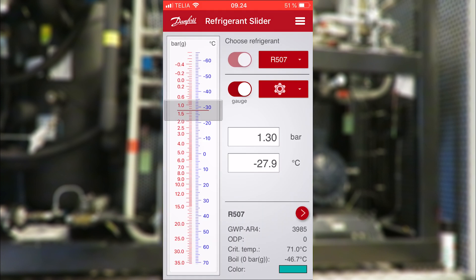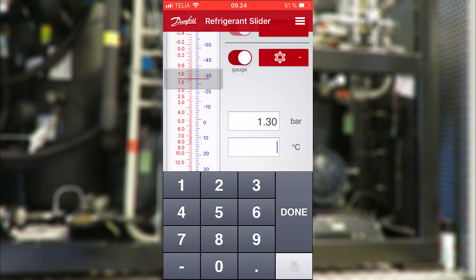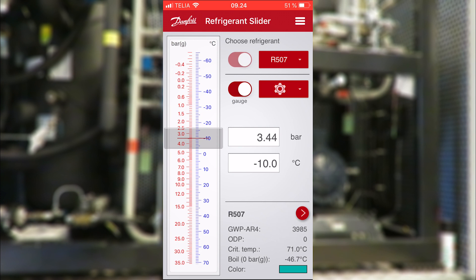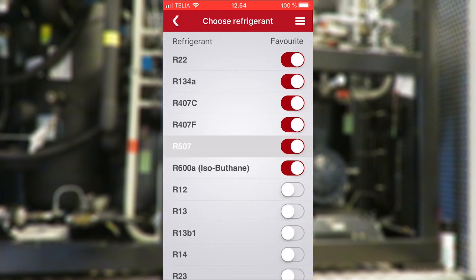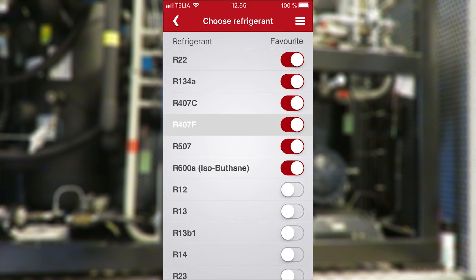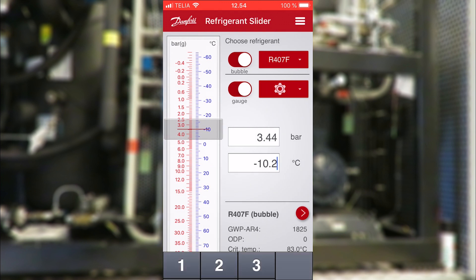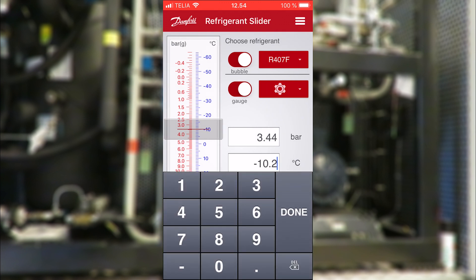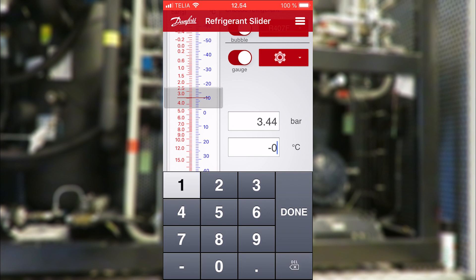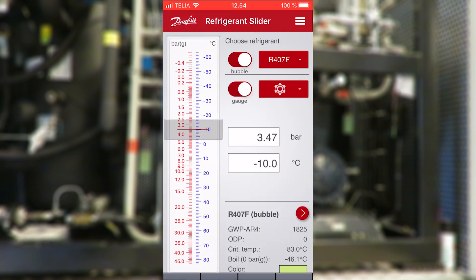Let's first enter the evaporating temperature of minus 10 degrees Celsius to see what the operating low pressure looks like. That's 3.44 bar. So let's compare with R407F. When we look at the list of refrigerants, you can see the R407F has been pulled up to the top of the favorites, so it's quite easy to switch between the two. You can see that the evaporation pressure is slightly higher with R407F, but it's so little that it doesn't make any practical difference.